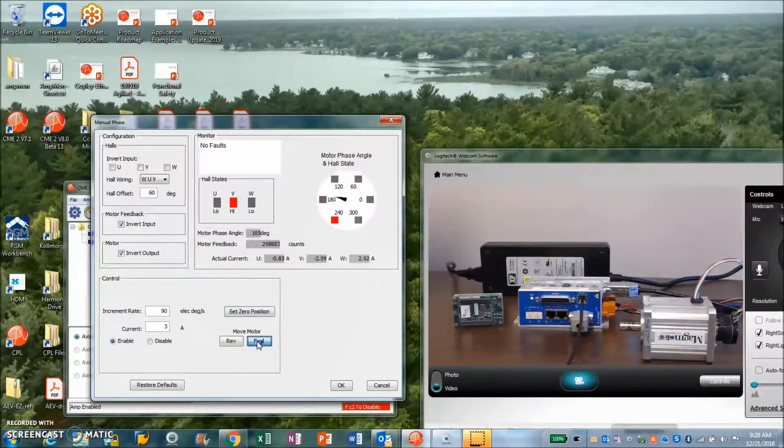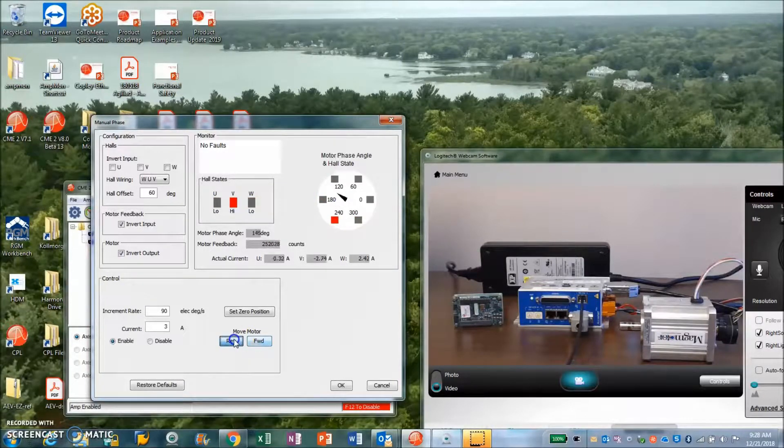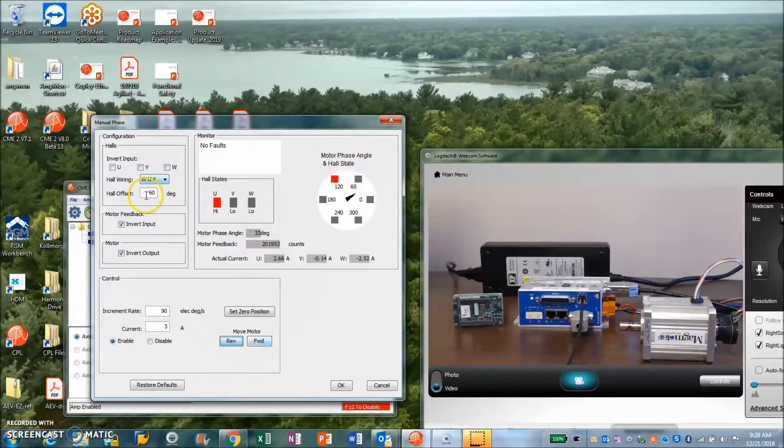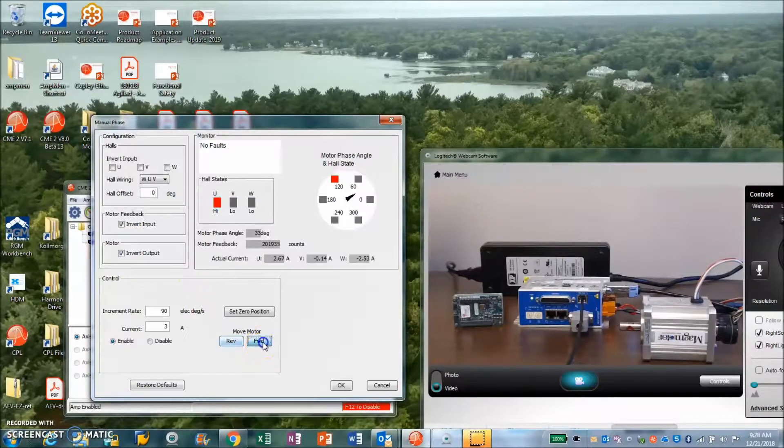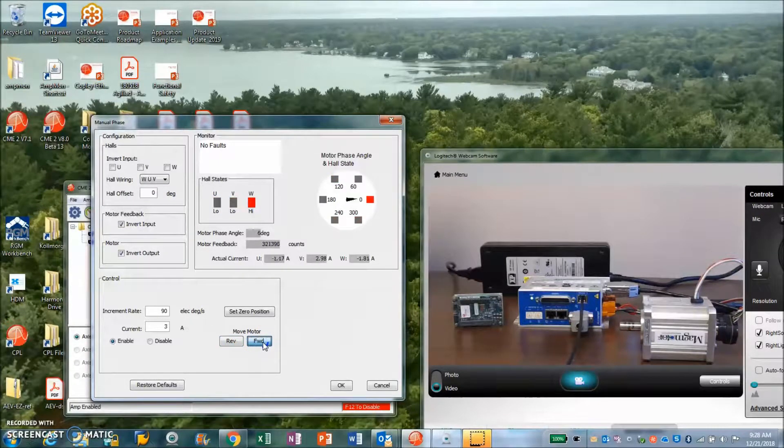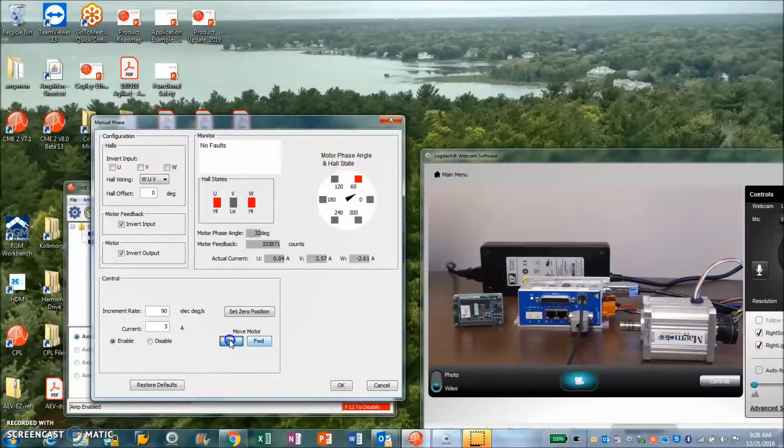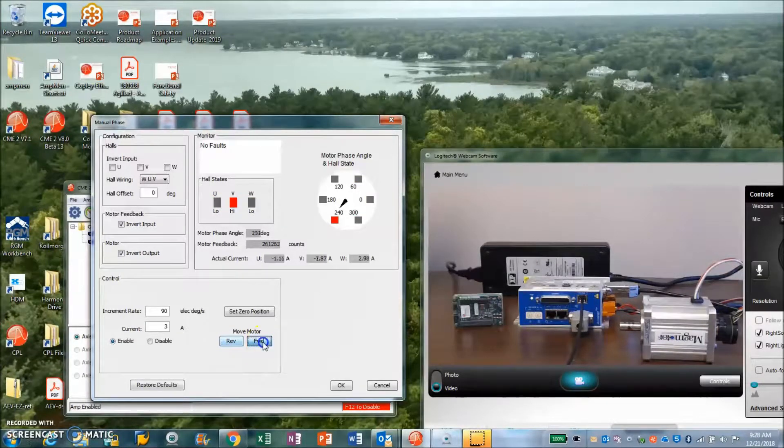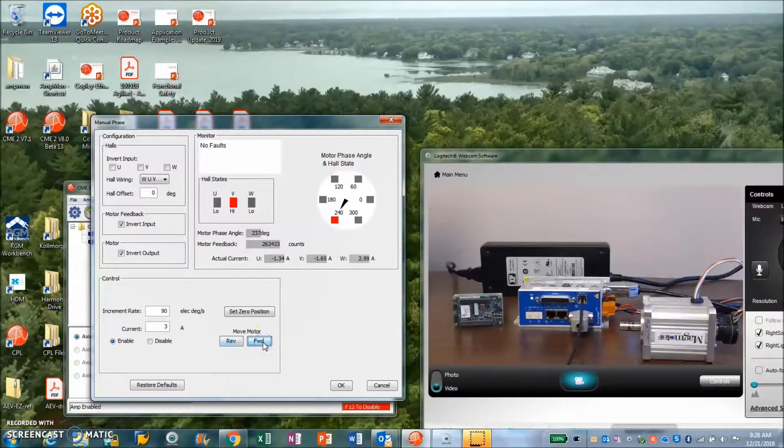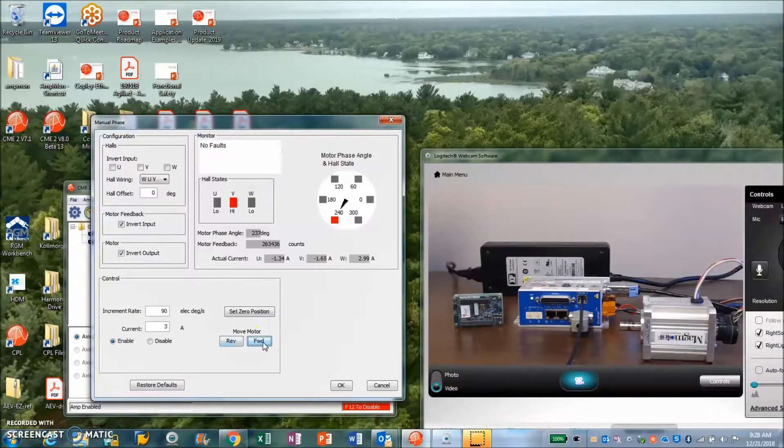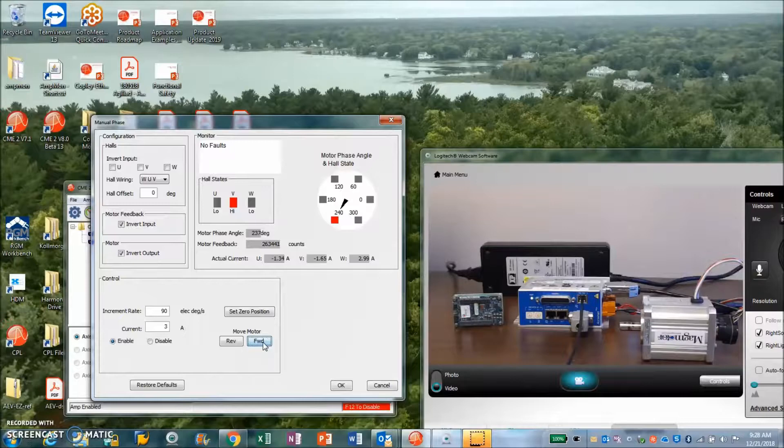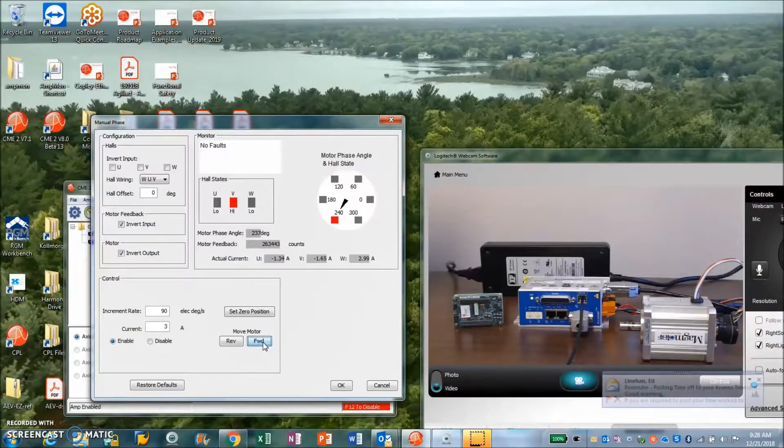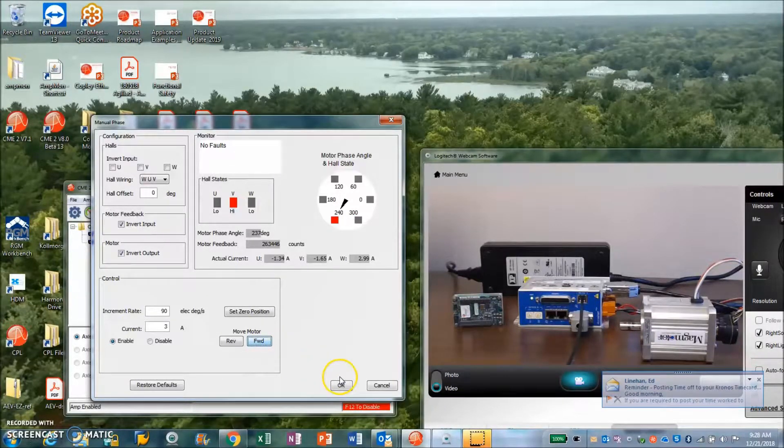If we had a hall offset adjustment, we would do that after we install the encoder. You can see this is a wicked lead and a wicked lag. Adjust the hall offset to zero. I want one file I can save which is like used with this motor and then I can replicate it. This file can be used to manufacture this drive motor or this motor encoder combination and make all the motors the same. That's really important if you're going to be the motor manufacturer.